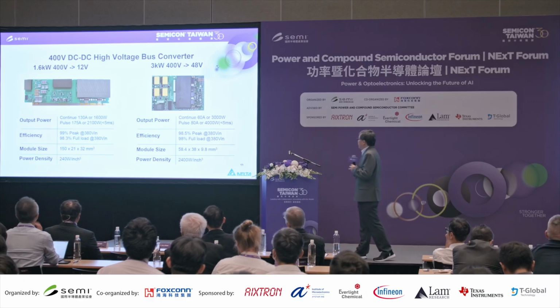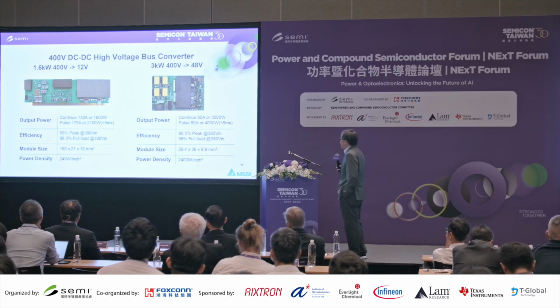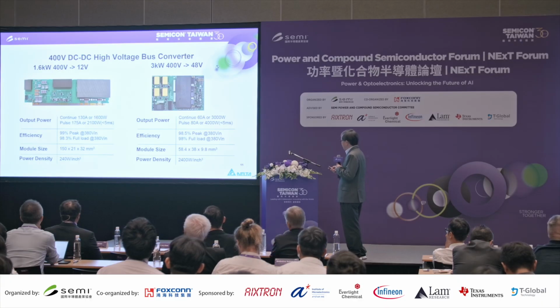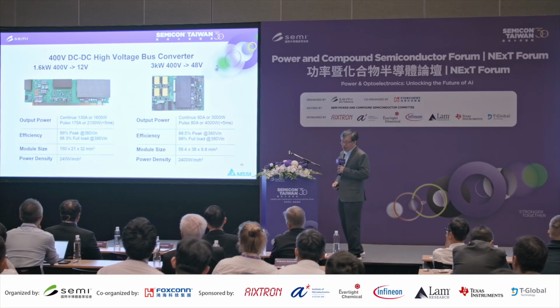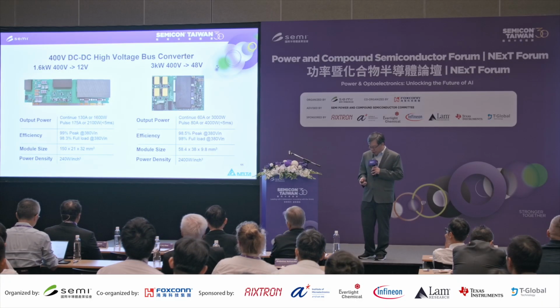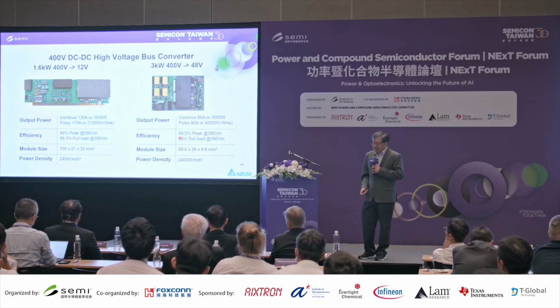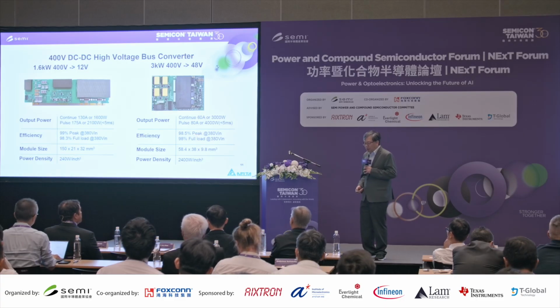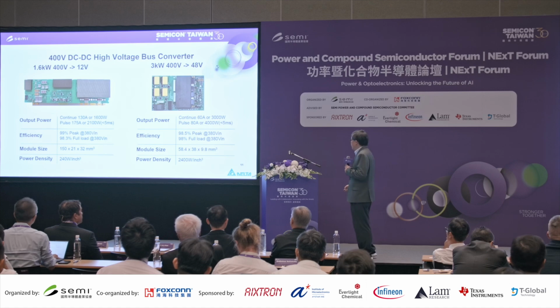Here I show a product we've realized at Delta that converts 400 volts into 48 volts at 3 kilowatts. You can see the performance reaches over 98.5% peak conversion efficiency, and the power density can reach 2.4 kilowatts per cubic inch.